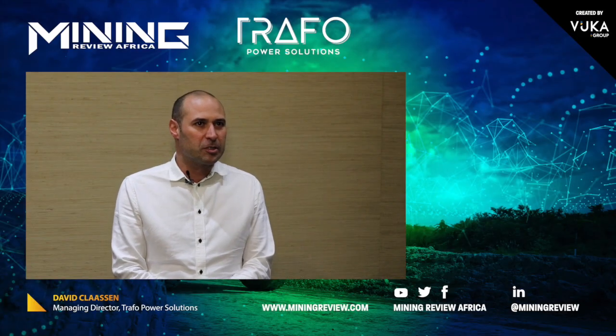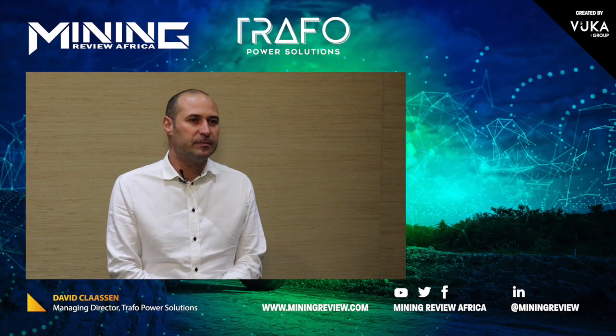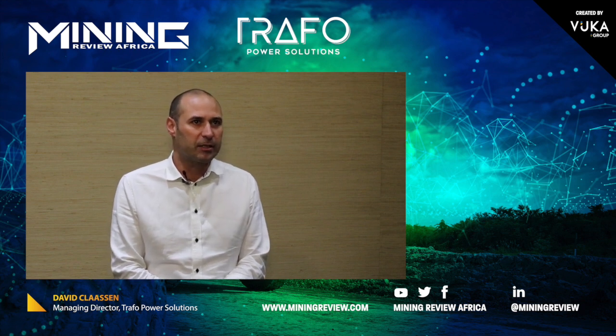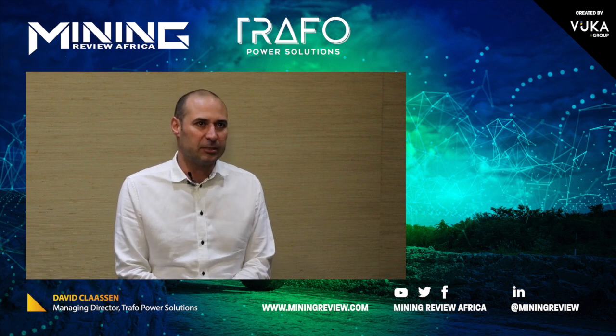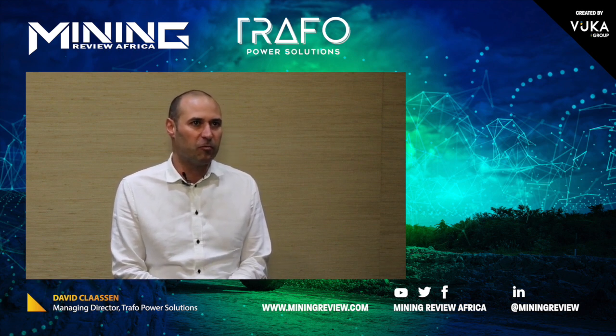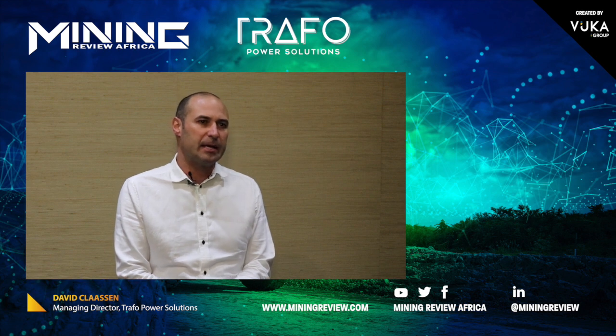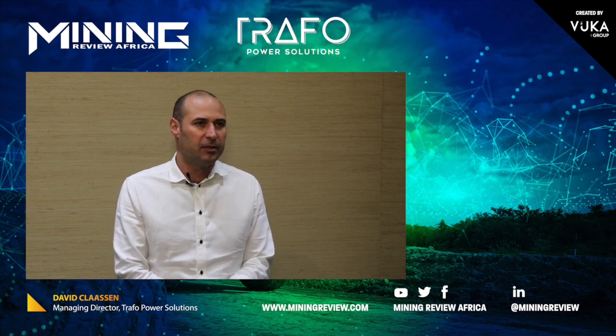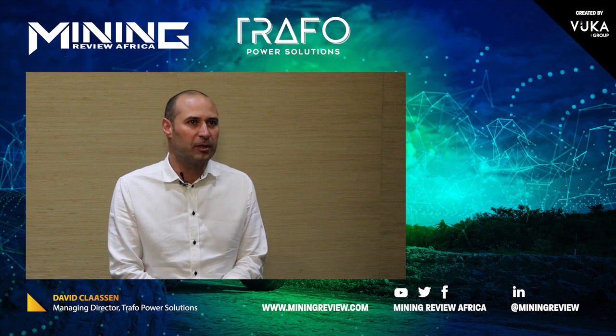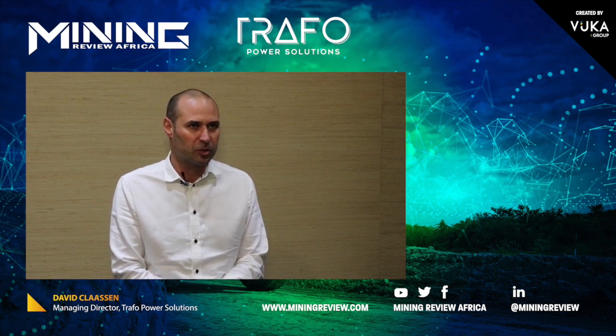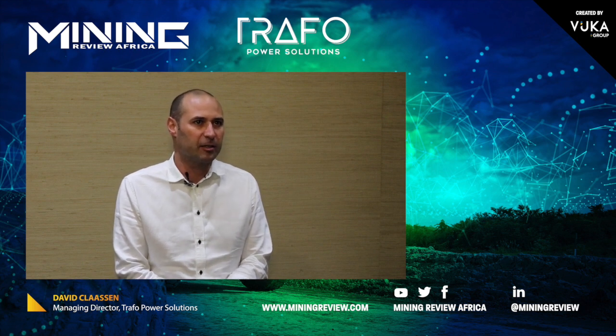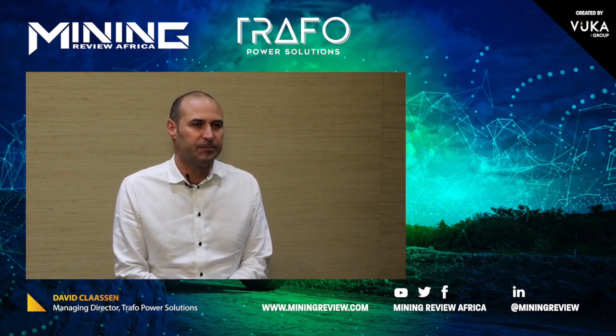It's critically important because the ability to keep water and dust out, which is what ingress protection measures, is the amount of dust and the amount of water that an enclosure can protect against. So it's very important that you understand the environment where the transformer is going. If you have a very high level of dust, you need to design an enclosure that effectively keeps all dust out, but at the same time allows you to cool the transformer adequately.